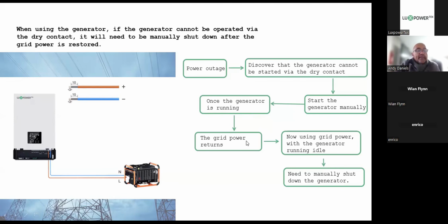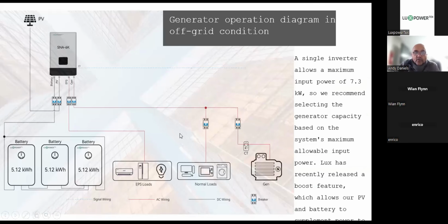And then when the grid returns, it will open the grid relay, close the generator relay, but it won't switch the generator off. So remember, this is for manually stopping and starting a generator. You physically have to go to the generator and shut it down. That's in manually started and stopped generators. Right, so operation diagram of the off-grid situation. So this is off-grid for a generator. Here you can see the client's got PV, he's got batteries, he's got a generator. The generator is going to the gen input.